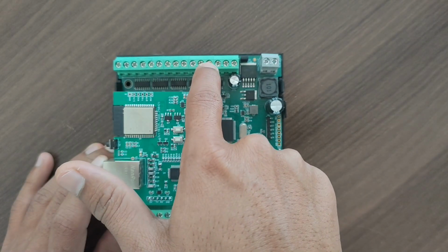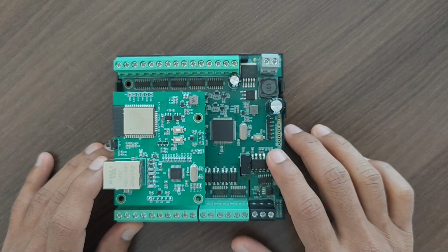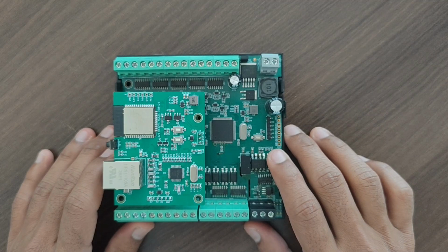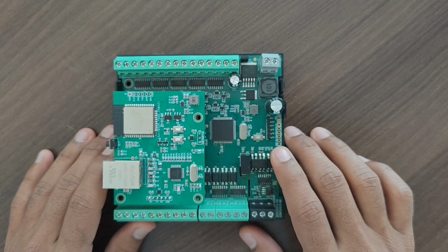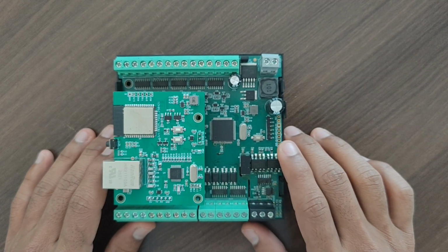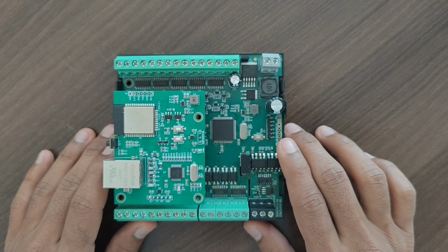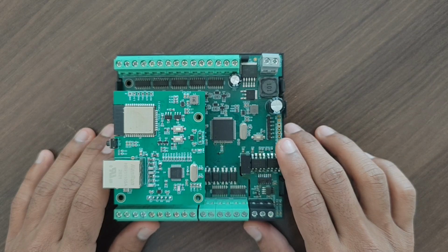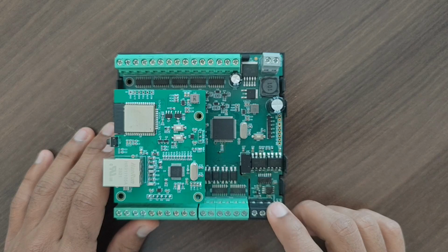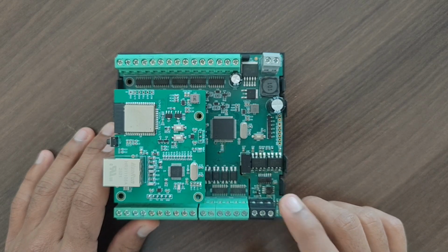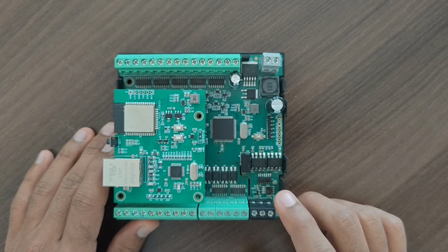In this UI, we have two provisions. For analog input, you can connect 0 to 10 volt, and also we have the configuration as 4 to 20 milliampere. For the different configuration, the board will get modified. And here we have the RS485 part. Here you can connect the slaves to get the data.